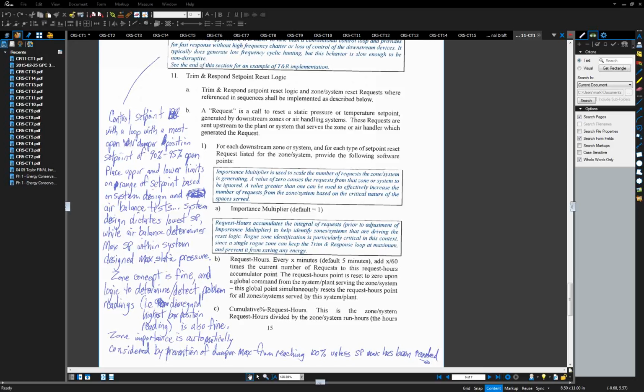and we've done it with Siemens and Johnson and many other controls. It's part of our internal standards. But one of the things we like about this is if you have something that's really important, you can use what's called the importance multiplier, and it actually gets more votes. If you've got a data center or some mission critical space, or a lab that you want to make sure is satisfied, you can give it a higher importance multiplier, and it basically gets a larger vote than all of the other VAV boxes, or coils if you're using trim and respond on coils as well.